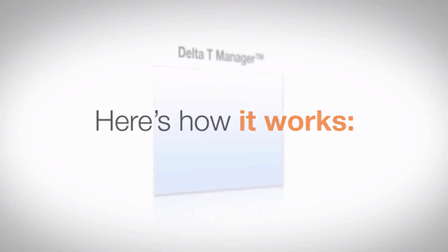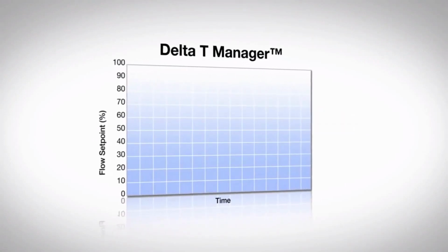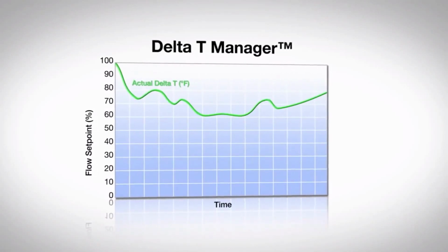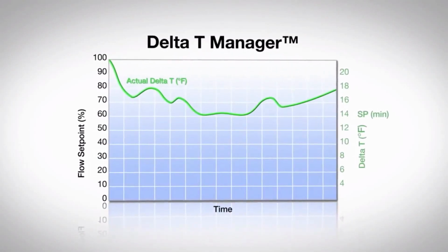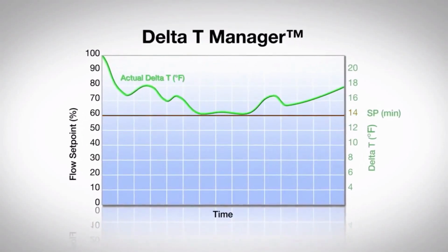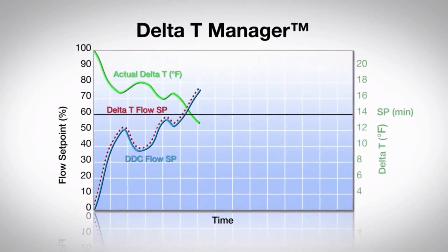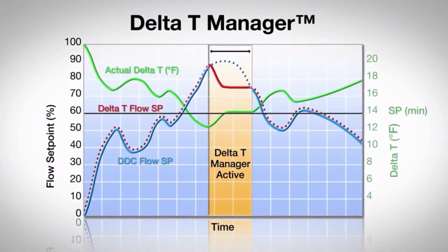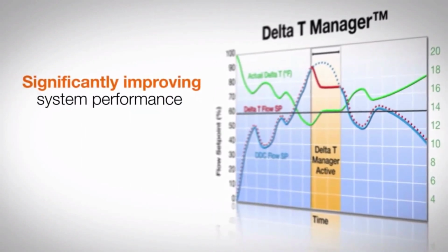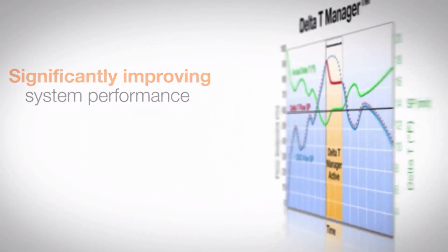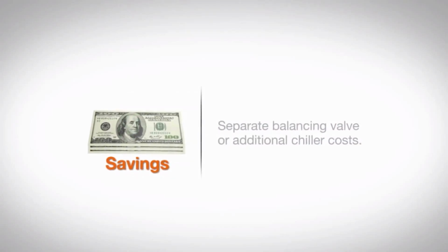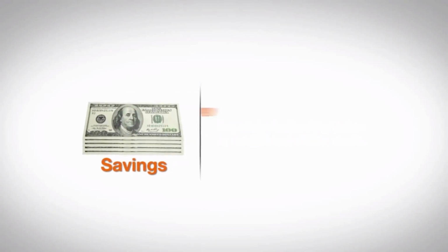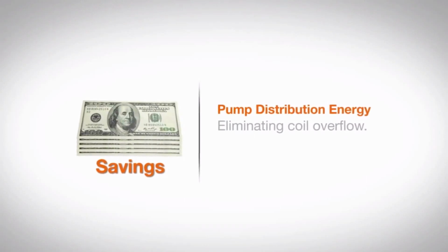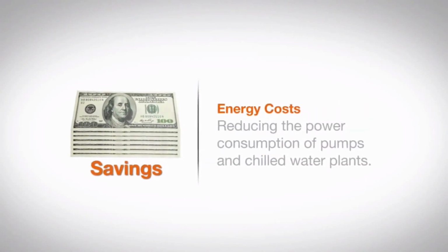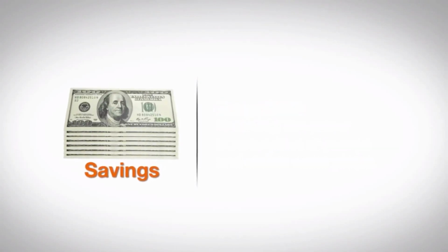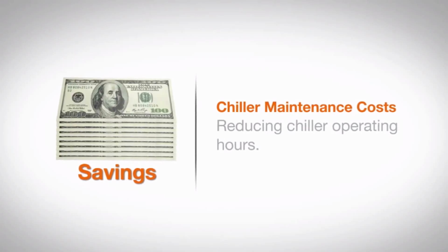Here's how it works. The proprietary built-in delta T manager continuously measures the differential temperature of both the supply and return water, the delta T, across the valve and compares it to the desired delta T set point. If the actual delta T drops below the set point, the valve modulates the flow, thus optimizing delta T at the coil and significantly improving system performance. All of which translates to savings on the costs associated with needing a separate balancing valve or additional chillers, on pump distribution energy by eliminating coil overflow, on energy costs by reducing the power consumption of pumps and chilled water plants, and on chiller maintenance costs by reducing chiller operating hours.